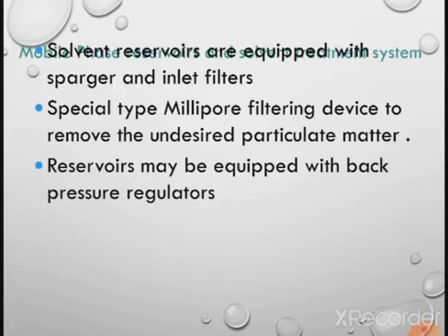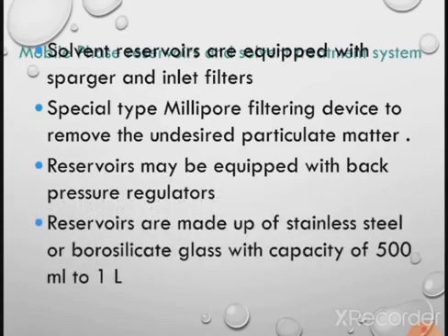Reservoirs are made from stainless steel or borosilicate glass, with different capacities from 500 ml to 1 liter, and in some cases from reinforced nylon, and they are coated with an inert layer so that they do not interact with the mobile phase.